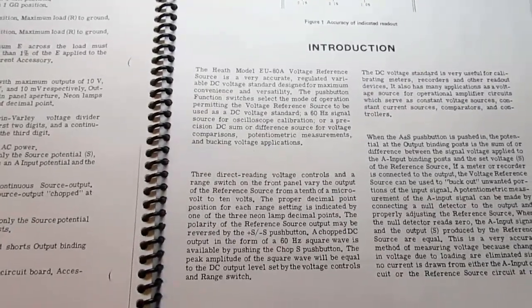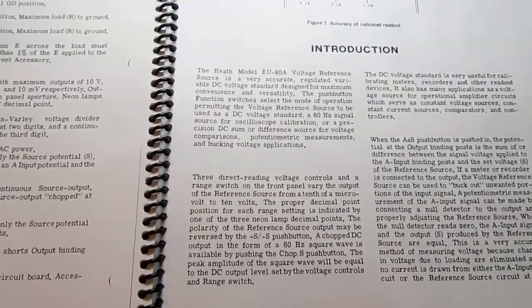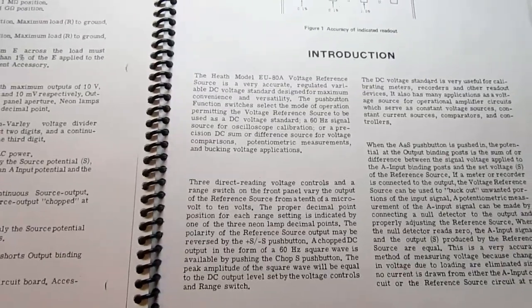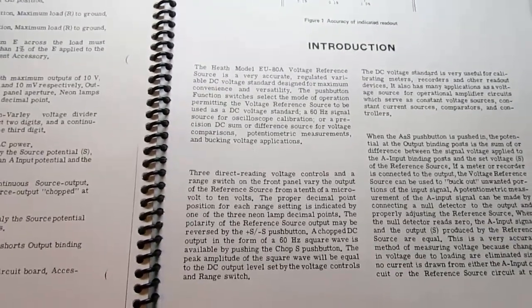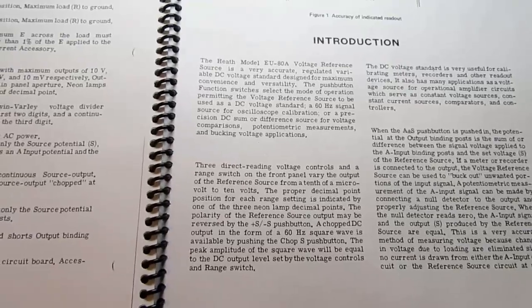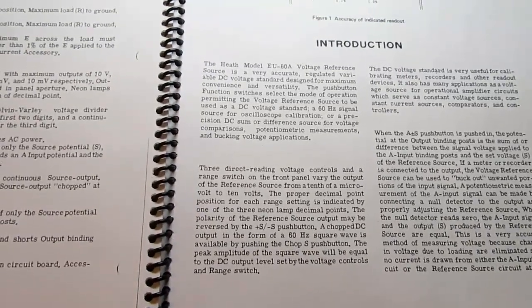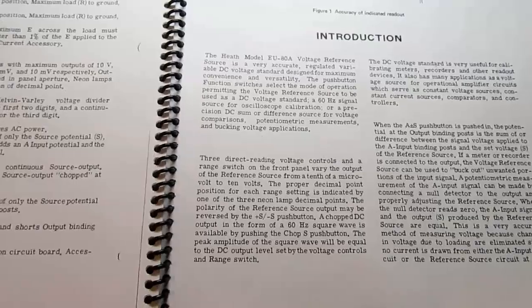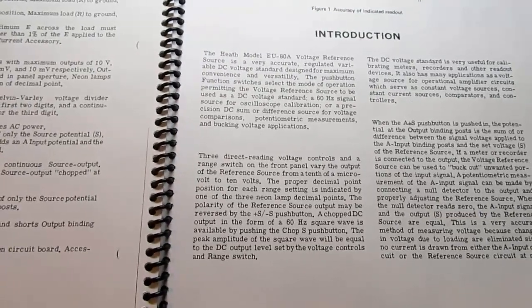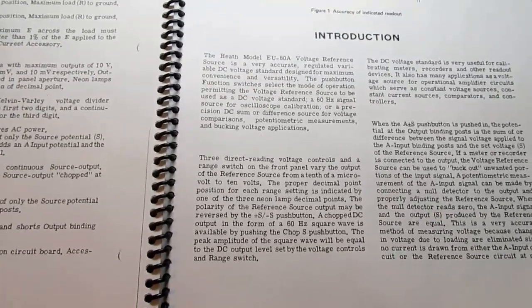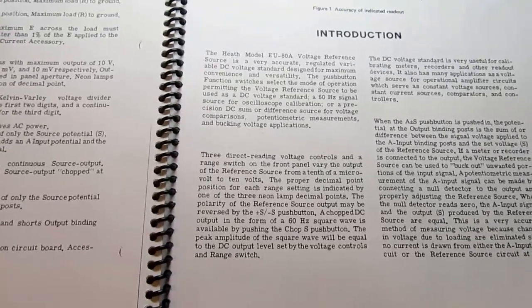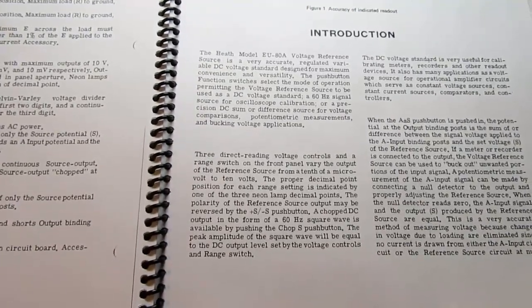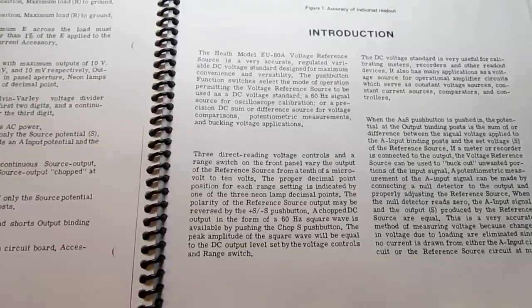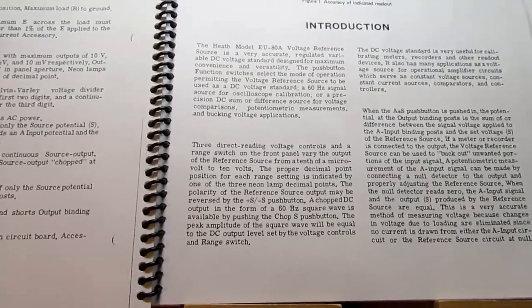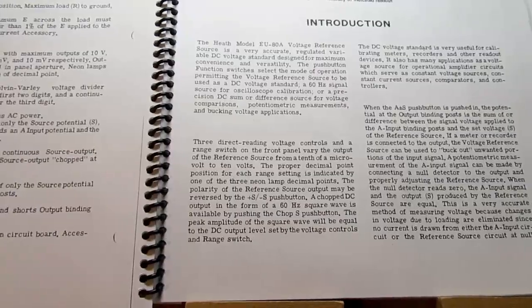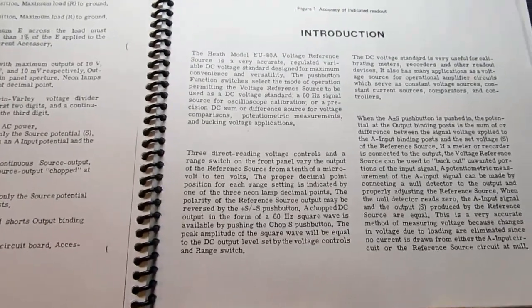3 direct reading voltage controls and a range switch on the front panel vary the output of the reference source from 1/10 of a microvolt to 10 volts. The proper decimal point position for each range setting is indicated by one of 3 neon lamp decimal points. The polarity of the reference source output may be reversed by the plus S minus S push button. A chopped DC output in the form of a 60 Hz square wave is available by pushing the chop S push button. The peak amplitude of the square wave will be equal to the DC output level set by the voltage controls and range switch.